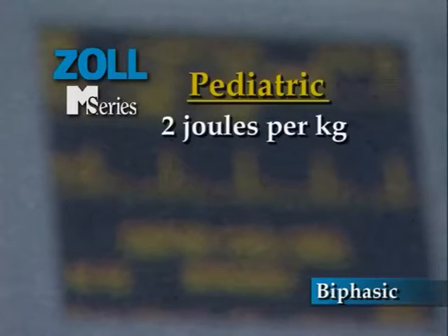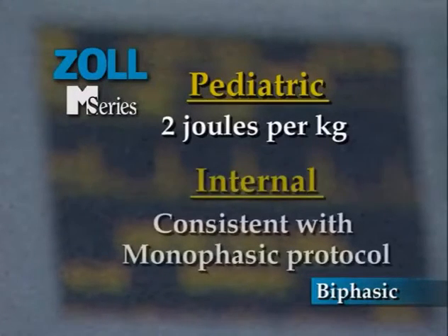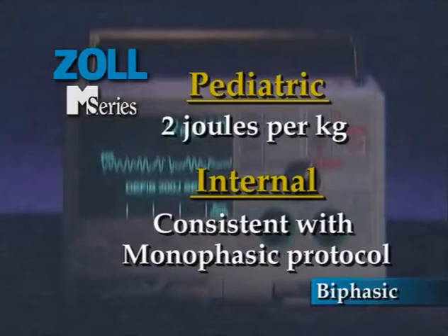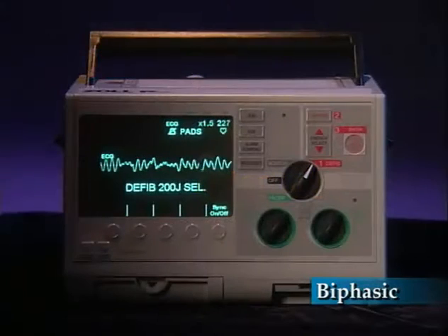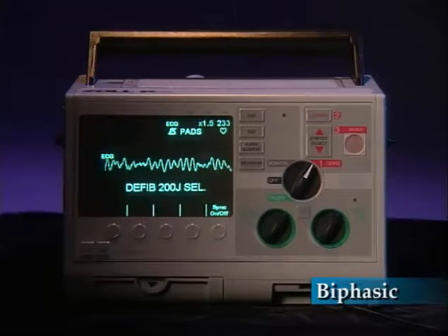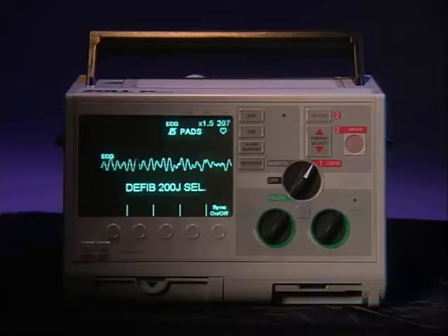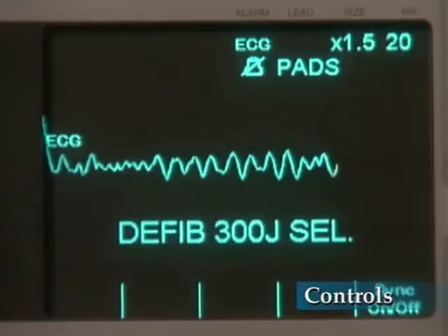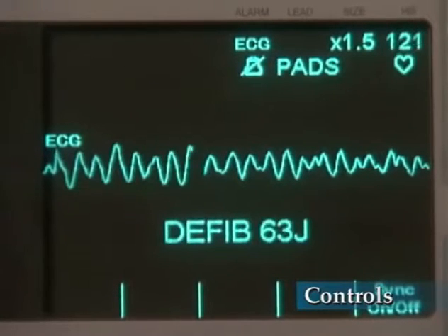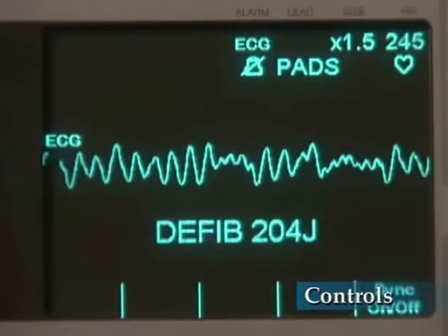Recommended pediatric settings should remain consistent with monophasic joule settings. Users should consult your medical authority to confirm pediatric settings. Biphasic energy levels for internal defibrillation should also remain consistent with monophasic protocol, unless otherwise directed by your medical authority. This video depicts the use of monophasic defibrillators. Other than energy levels, there are no operational differences between monophasic and biphasic M Series devices. The default energy levels for first, second, and subsequent shocks are 200 joules, 300 joules, and 360 joules.